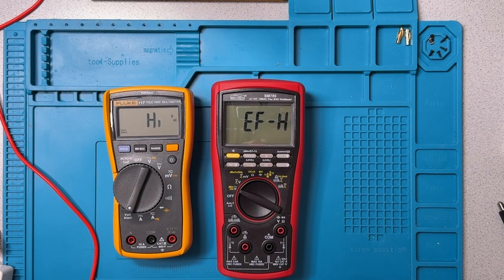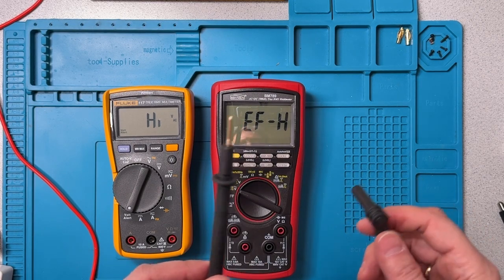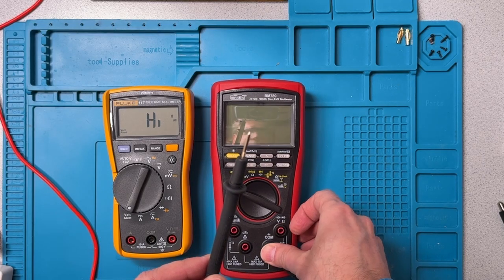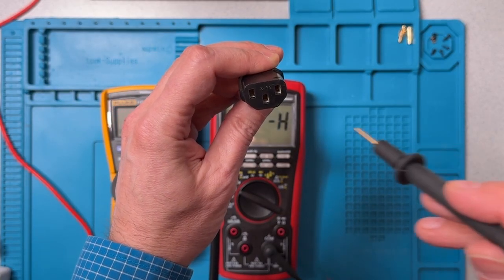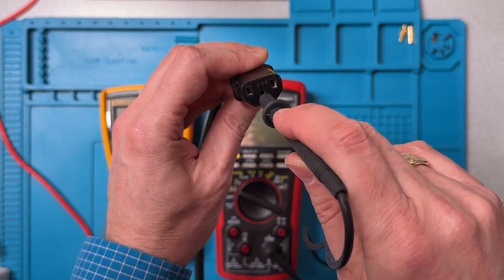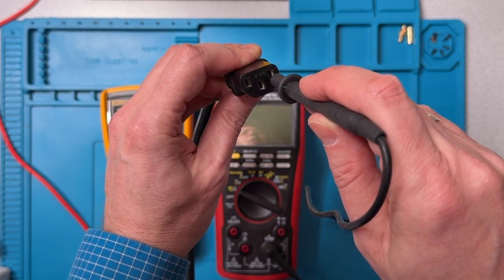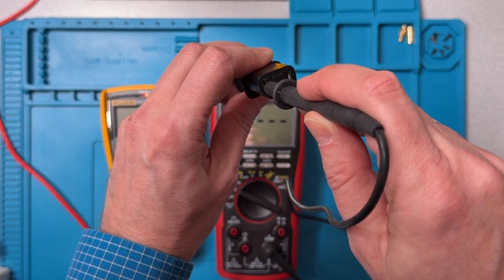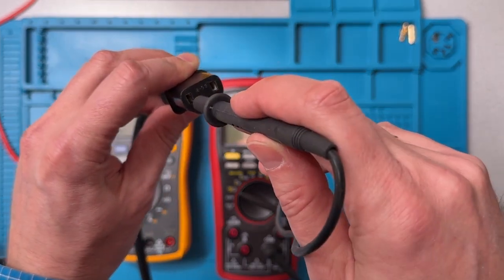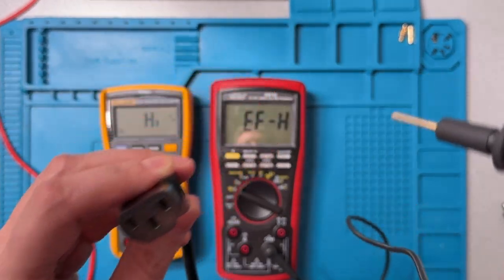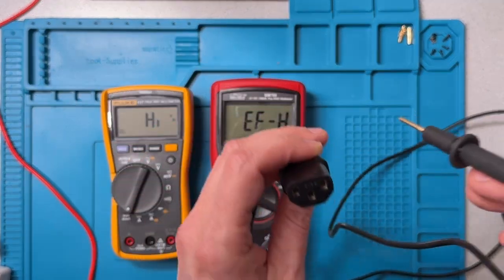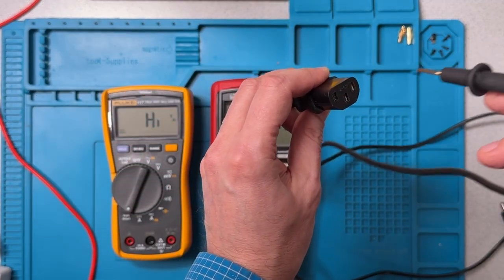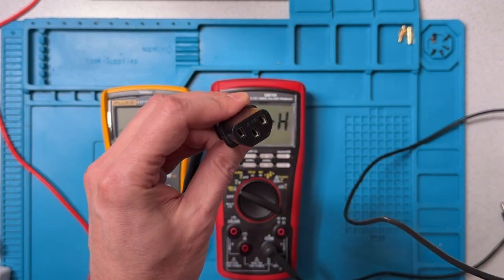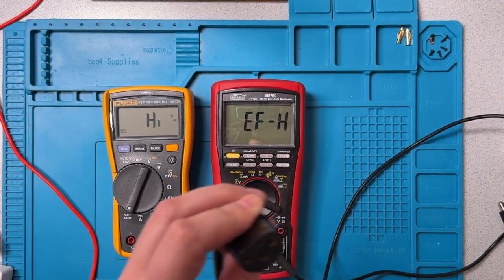The Brymen also has a live wire detection feature. And so we take, usually the ground cord, we plug it in here. And now we can take this probe and we can stick it in to a socket here. So ground, that shows a little bit of ghost voltage. Neutral, a little bit of ghosting. But the live really reacts quite right away. And in fact, when we have the live, it sets up enough of a field that even the Fluke detects that there's a current flowing there. And so that's how the hot wire detection works on the Brymen.